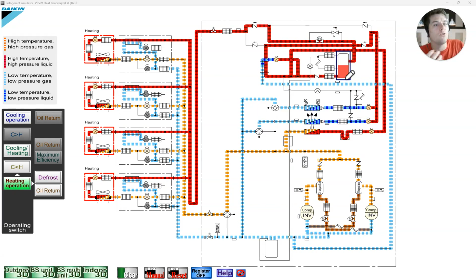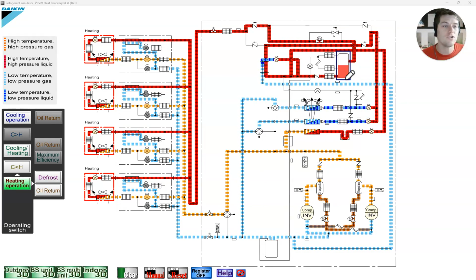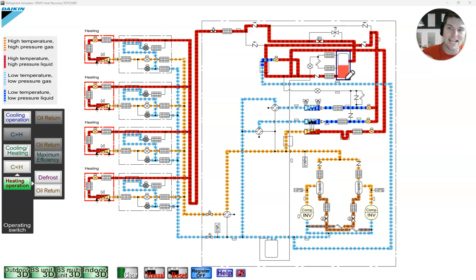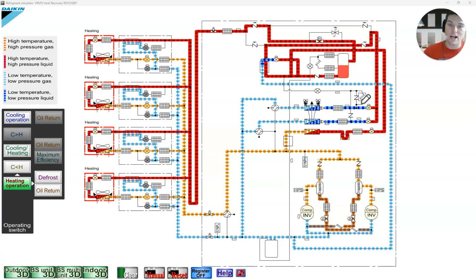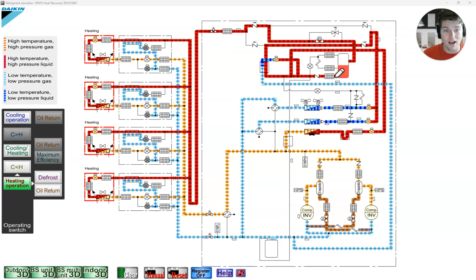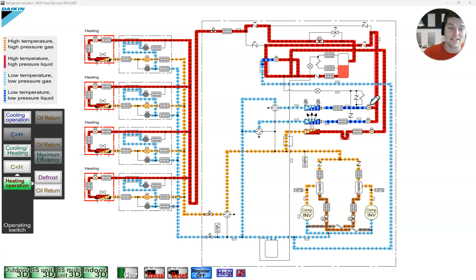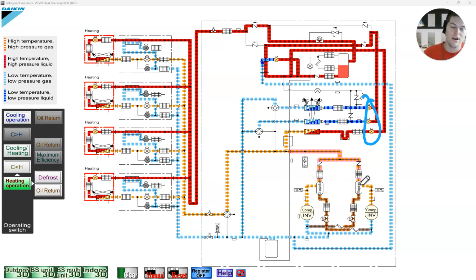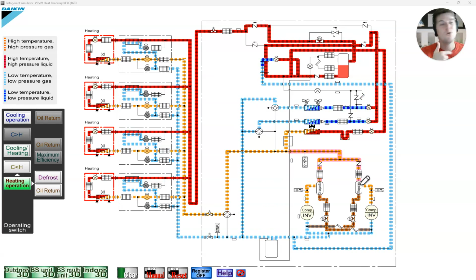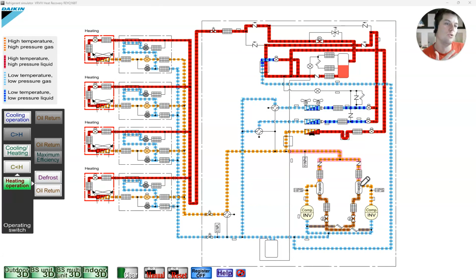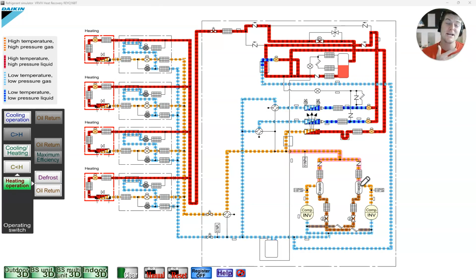They generate and they stack liquid. They take it, they hold it. It's a storage tank for liquid. If there is no liquid in there and there's barely any liquid coming into it, over time, it's going to boil off into a low pressure state because again, we're not metering any refrigerant here. We have a high suction superheat. We have an insanely high discharge superheat. And we have no subcooling on our indoor units. And my liquid line is a suction line now, right?